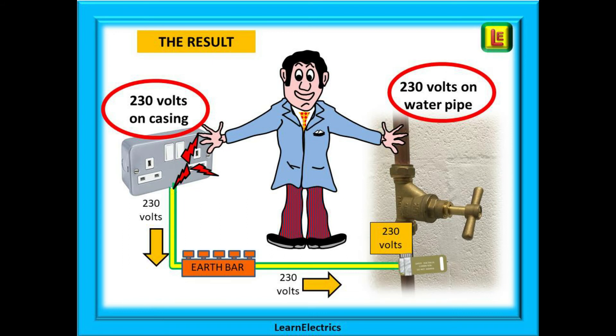We have shown this example as a supplementary bonding conductor, but it is exactly the same sequence of events if it was a main protective bonding conductor through the earth bar or the main earth terminal in the consumer unit. 230 volts travelled from the point of fault to all the connected metalwork in the property — everything rises to 230 volts — and then just as quickly the fuse blows and everything drops back down to zero volts, a condition of safety.